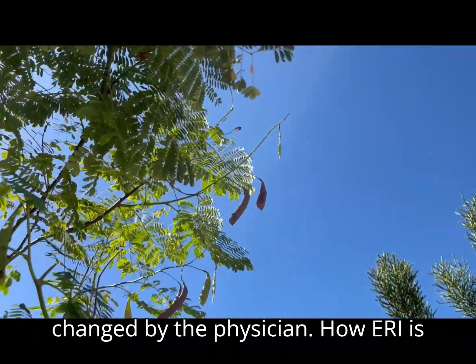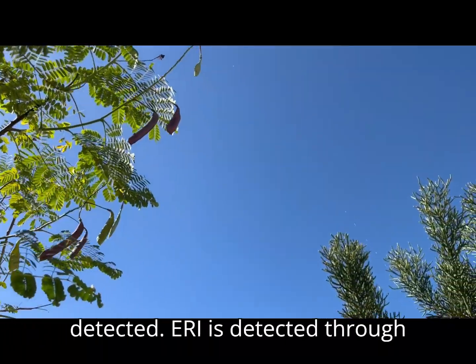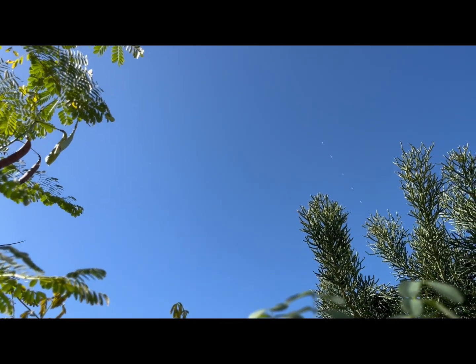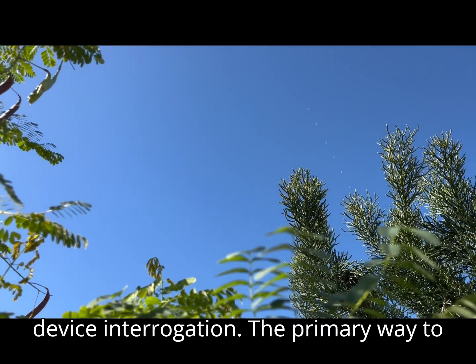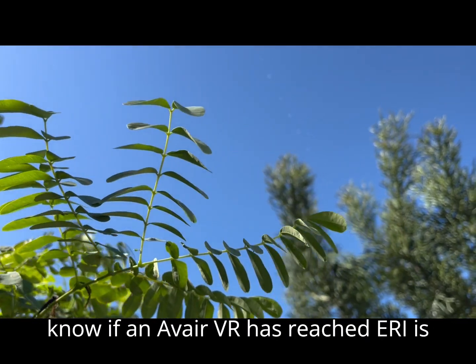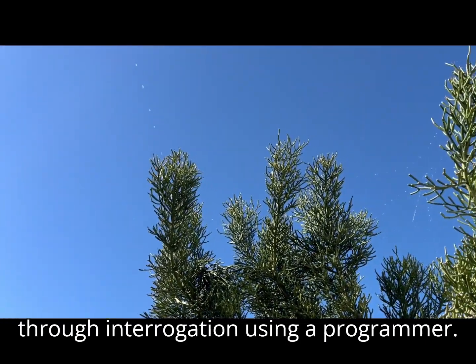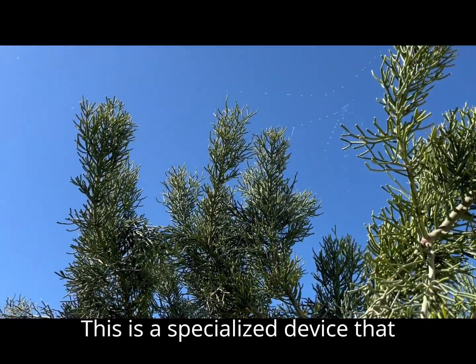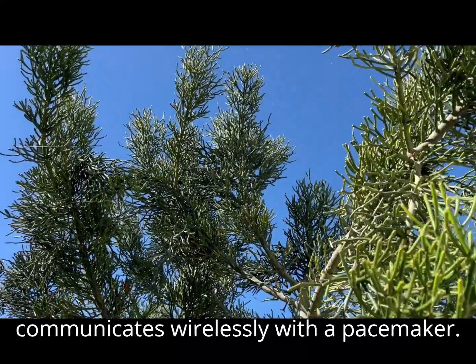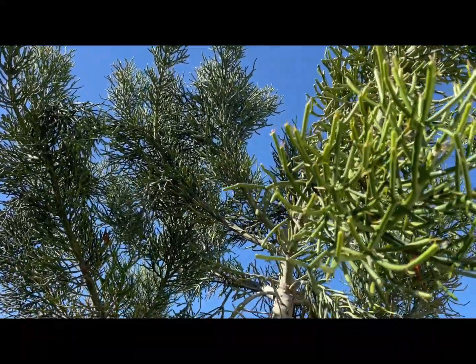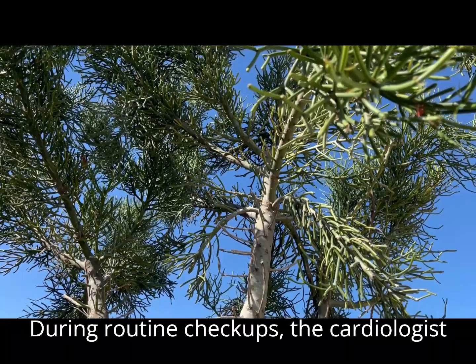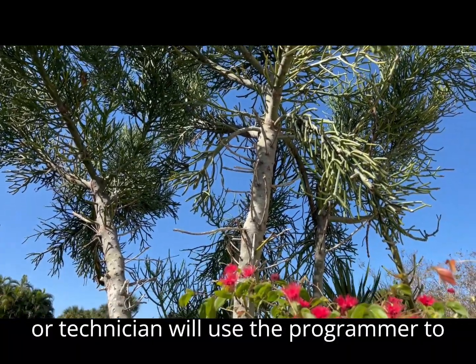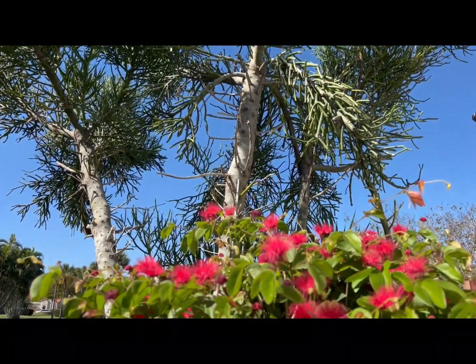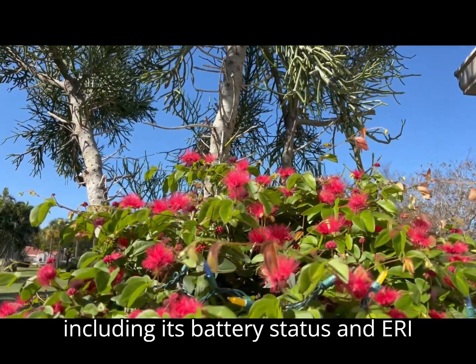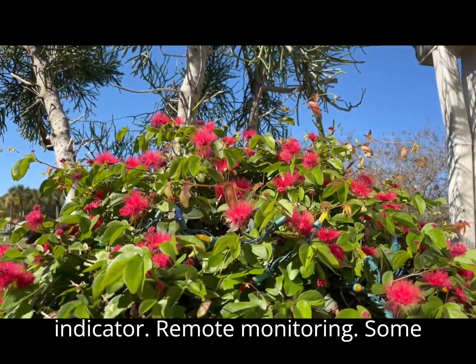by the physician. How is ERI detected? ERI is detected through device interrogation. The primary way to know if an Aveir VR has reached ERI is through interrogation using a programmer. This is a specialized device that communicates wirelessly with the pacemaker. During routine checkups, the cardiologist or technician will use the programmer to download data from the pacemaker, including its battery status and ERI indicator.